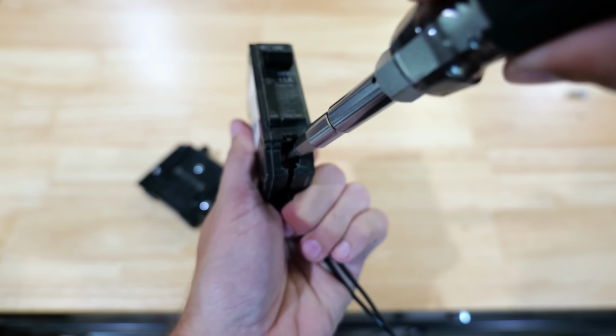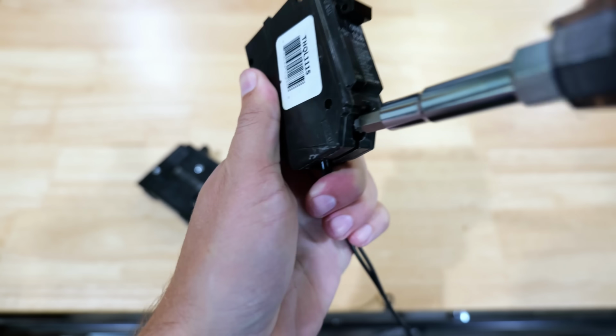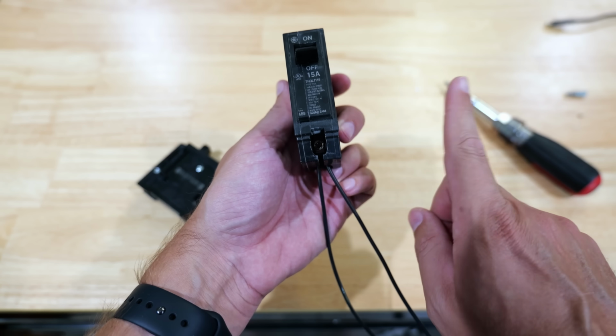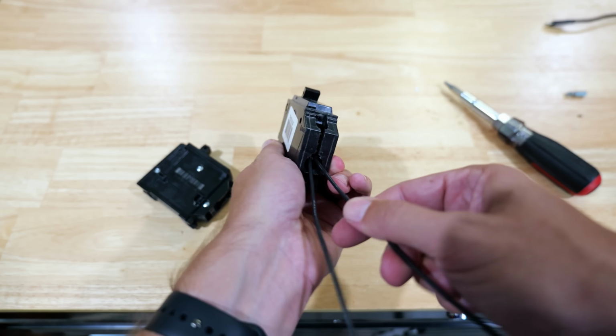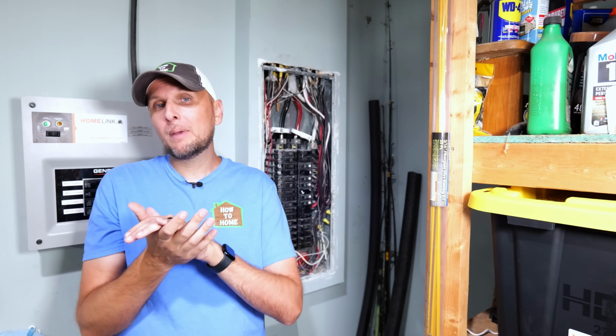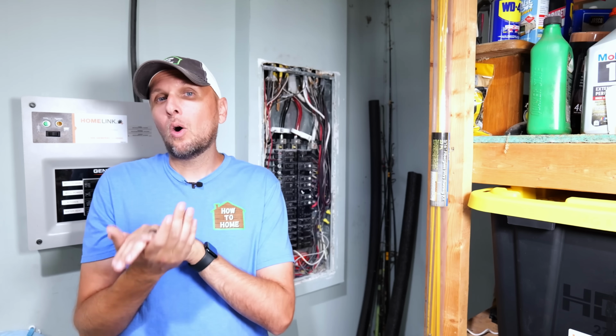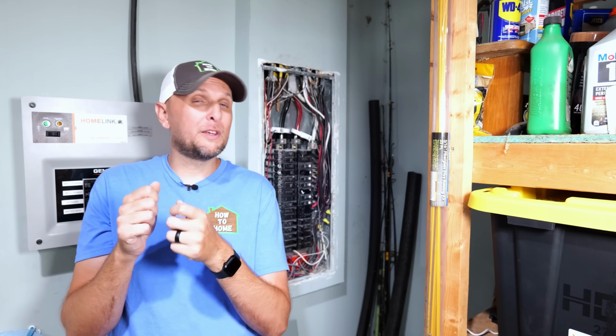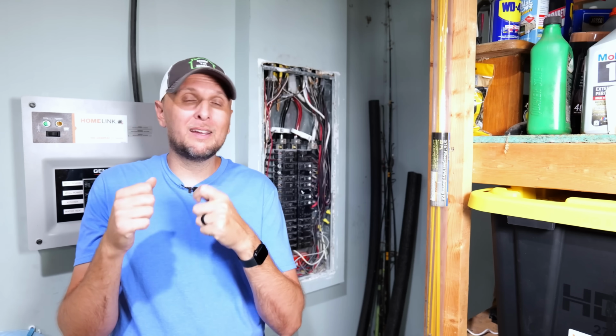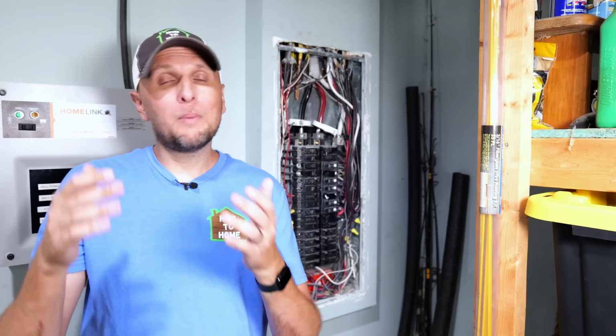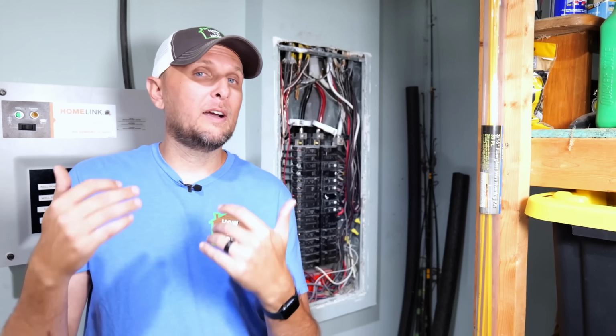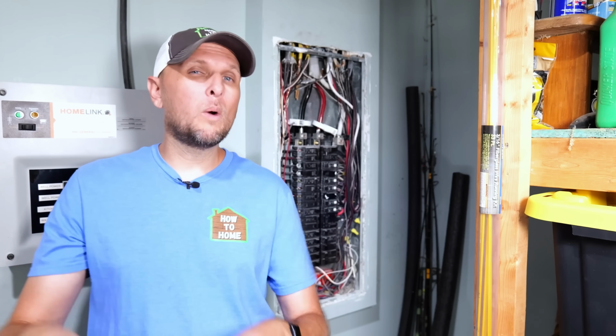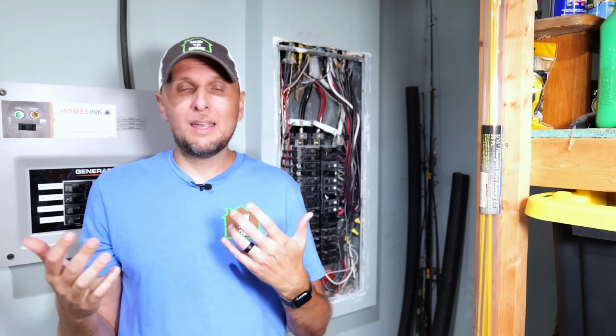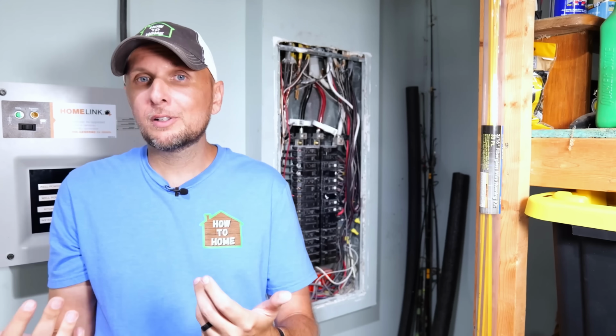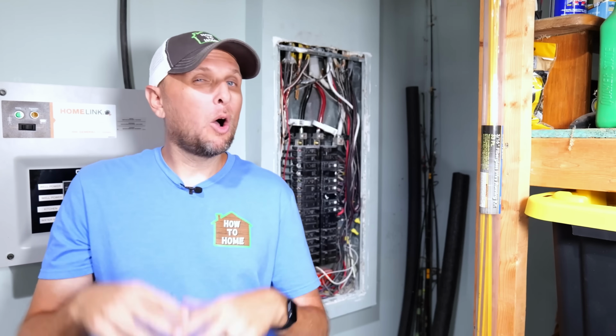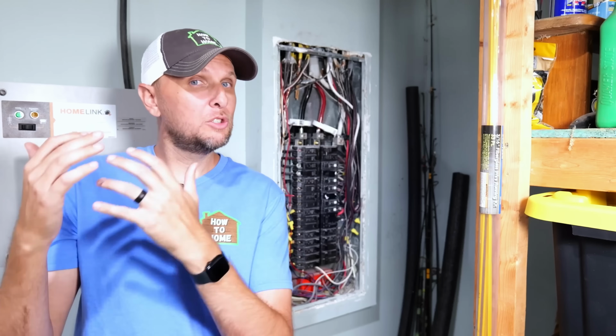And I will say, for the most part, in many ways, it will probably work, but you are running a very high risk of those wires becoming loose over time, because the clamping mechanism that's in it doesn't take a whole lot for those wires to get loose if there's any movement whatsoever, or if you didn't get the torque specs right. And so then you might have a loose wire, which can lead to a very serious issue. But in some cases, what is called double tapping, which is again putting two wires into one breaker slot, can be okay, but only if the breaker is designed to do so.